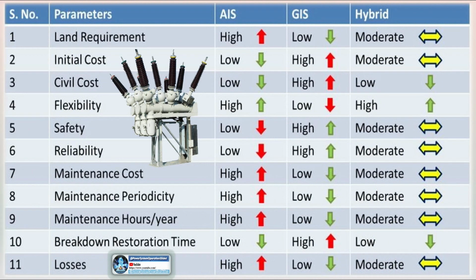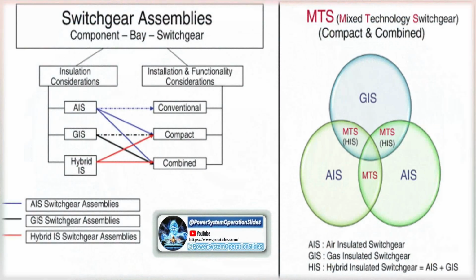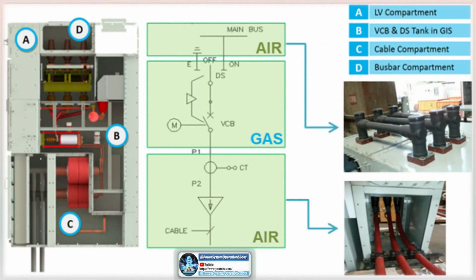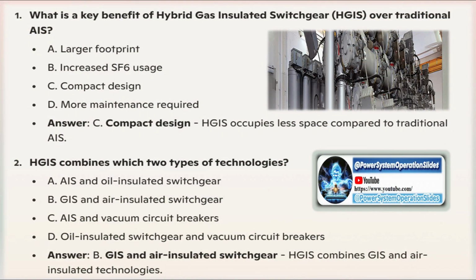Gas-insulated switchgear versus air-insulated switchgear. While both GIS and AIS serve similar functions, they differ mainly in their insulation mediums. Insulation medium: GIS uses gas, typically SF6, for insulation. AIS uses air for insulation. Advantages of GIS: compact and efficient. GIS is more compact and efficient, ideal for confined spaces. Construction: GIS components are housed in gas-filled, earthed modules, sealed for life. AIS components are generally accessible and withdrawable.